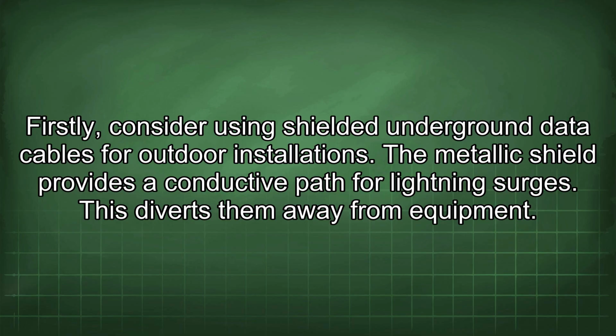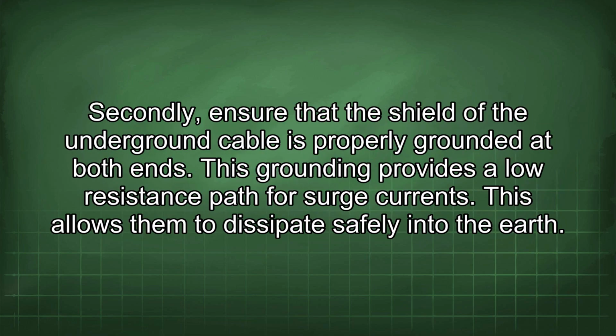The metallic shield provides a conductive path for lightning surges. This diverts them away from equipment. Secondly, ensure that the shield of the underground cable is properly grounded at both ends. This grounding provides a low-resistance path for surge currents. This allows them to dissipate safely into the earth.